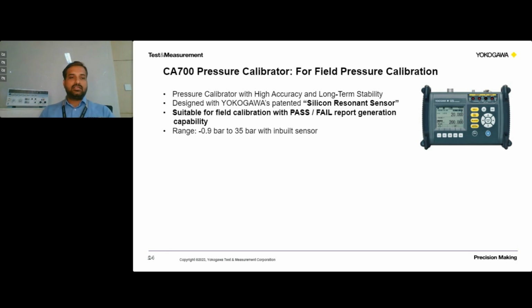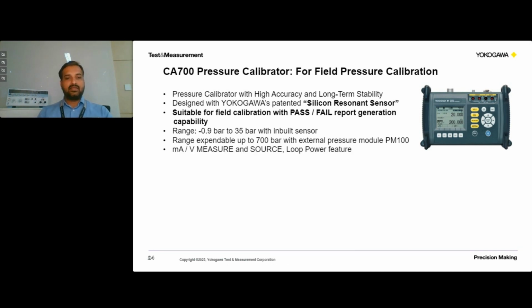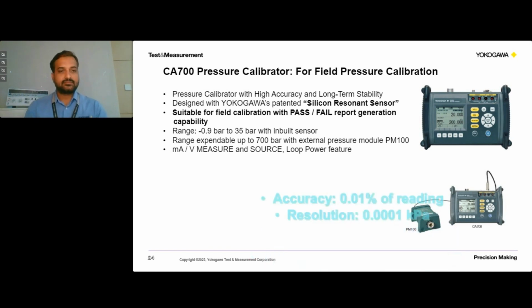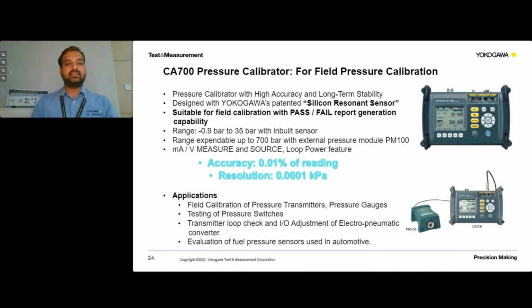In this, we have got a range from minus 0.9 bar in the vacuum to 35 bar in the positive pressure with an inbuilt sensor. It can be extended up to 700 bar with the external pressure module called PM100. It has also got source and measurement capability for milliamps and voltage, and it has also got a loop power feature. Accuracy is 0.01% of the reading, and resolution is also very high, 0.0001 kPa. This is more suitable for calibration of pressure transmitters and pressure gauges in the field, as well as for loop checking of the transmitters and evaluation of the pressure sensors in the automotive industry, those kinds of applications.